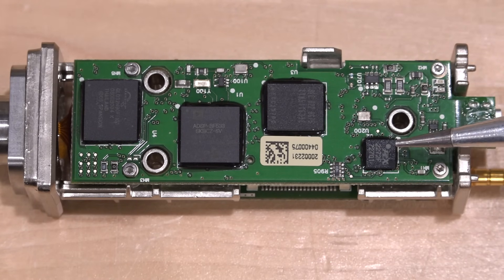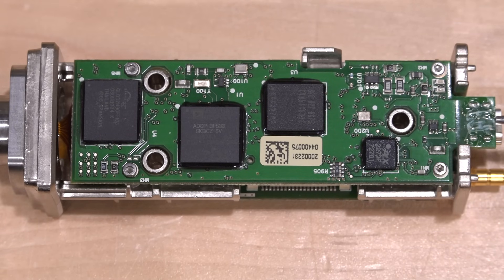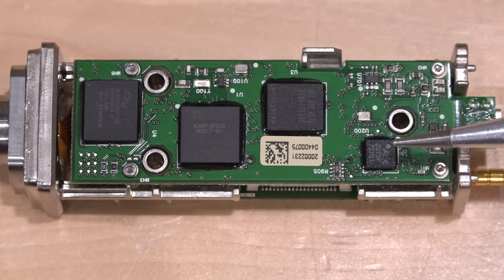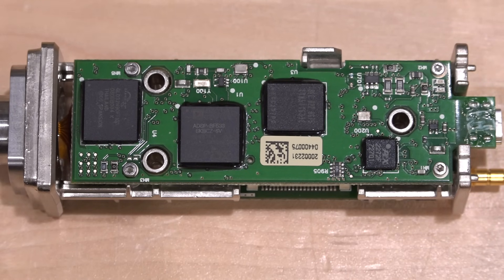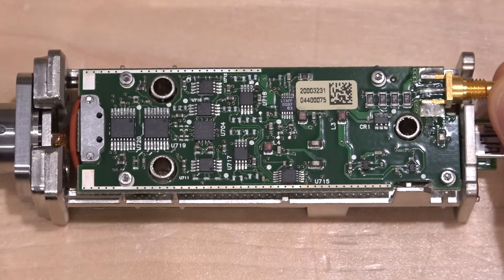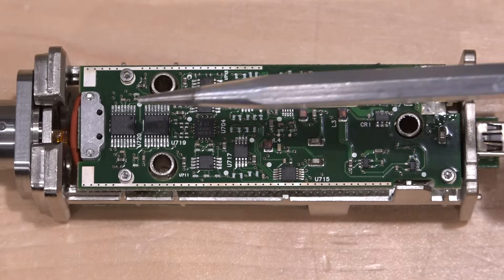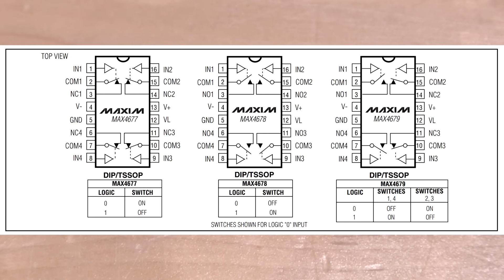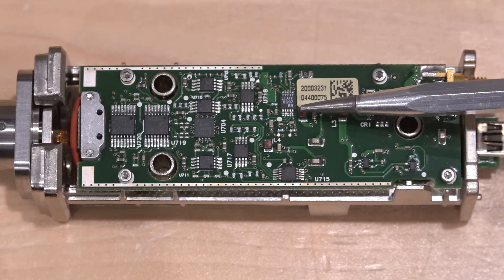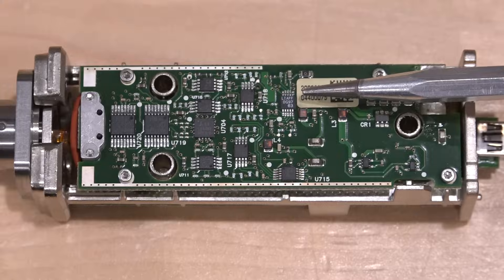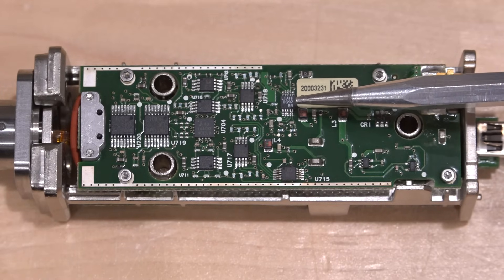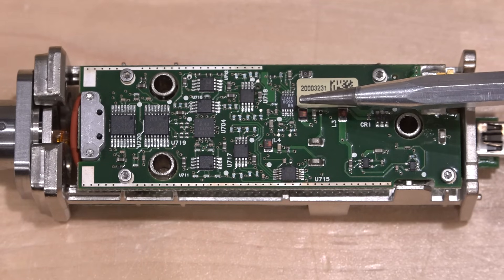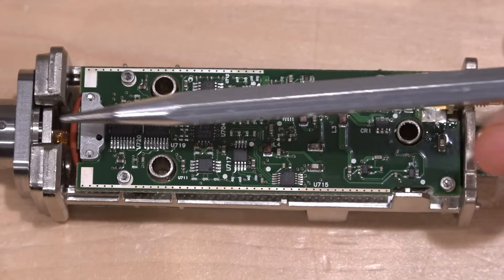Then here we have a USB 2.0 controller. All of this is essentially doing the functions of calibration, internal processing, passing the data back and forth. The LEDs are right over here connected to the light pipe. If you flip it to the other side, we'll see all the analog interface. This is a trigger port up here. We have some analog switches, switching back and forth depending on how the detector is working. Here in the corner, this tiny component is our ADC, a dual channel 1.5 megasample per second simultaneous sampling per channel, 12 or 14 bit resolution from Linear Technologies with a serial interface.